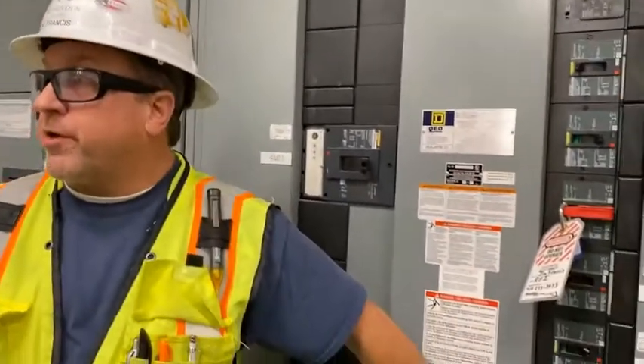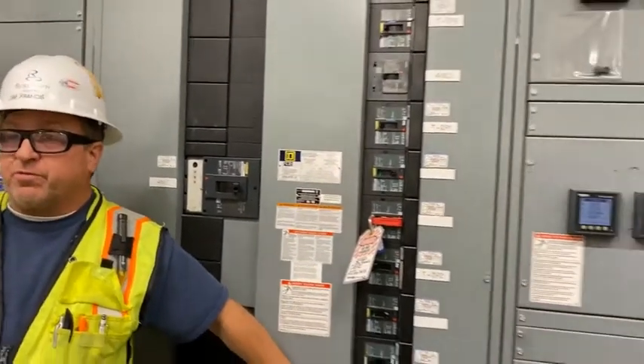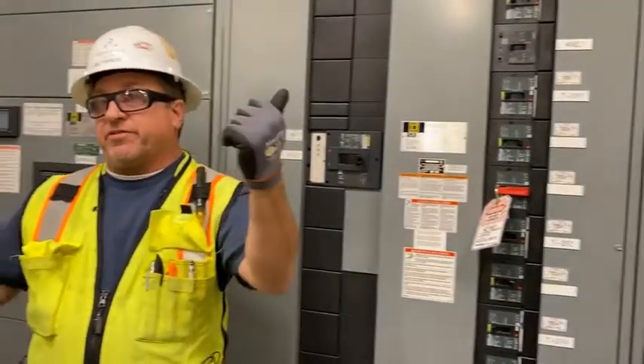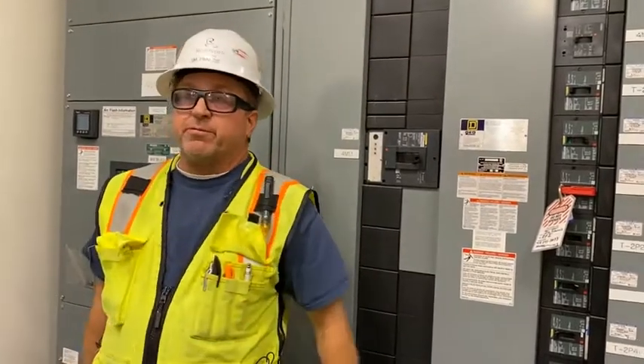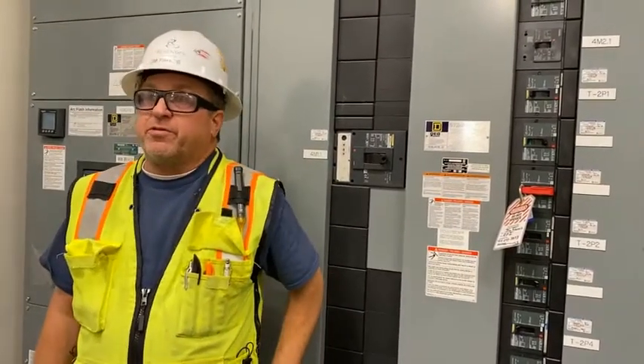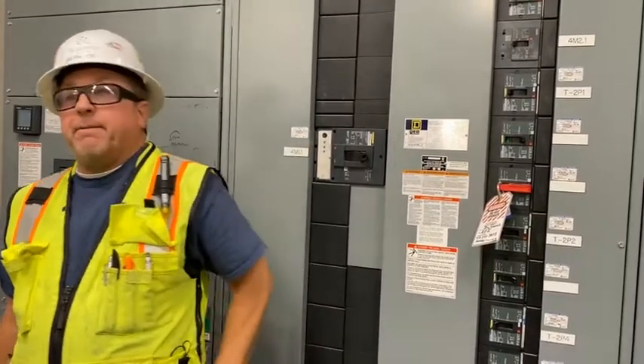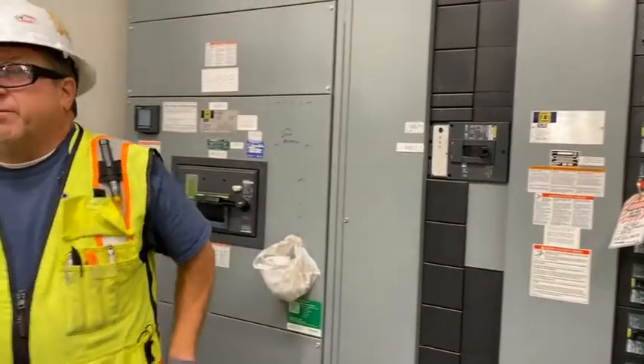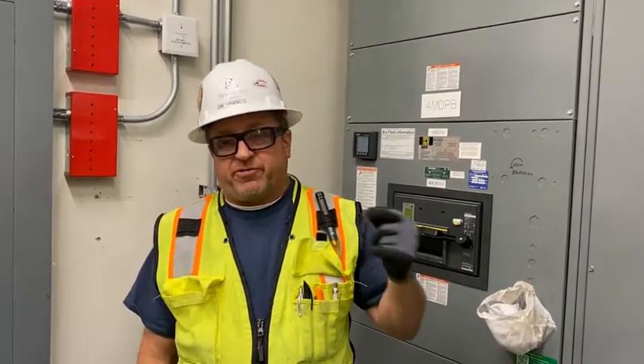So for instance, if you were to turn this breaker off, that ATS would lose normal voltage, send a signal, and within 8 seconds the generator would be refeeding it with the emergency panel. I believe it's actually around 6 seconds when we've been on a cold start. Once the generator's been running for a little while, it's almost instantaneous.